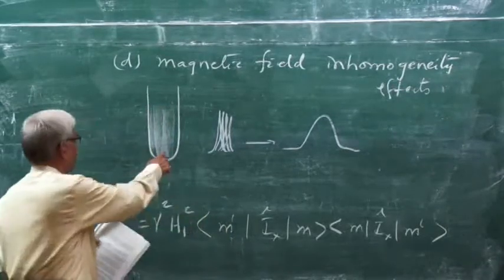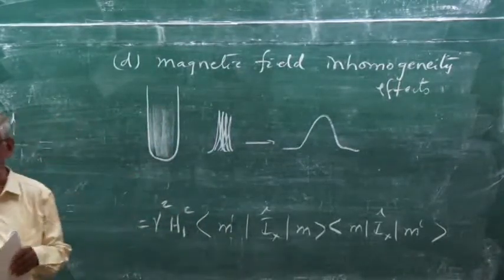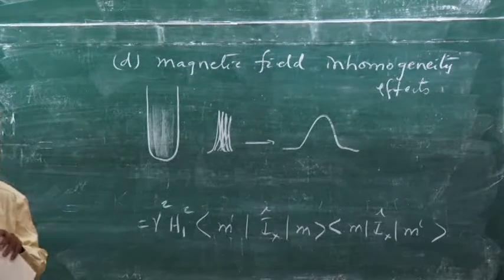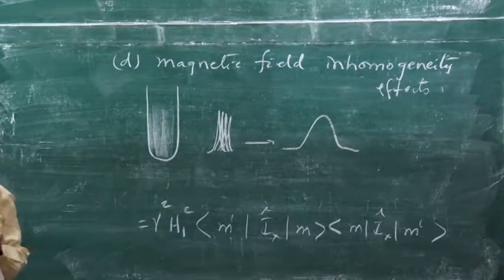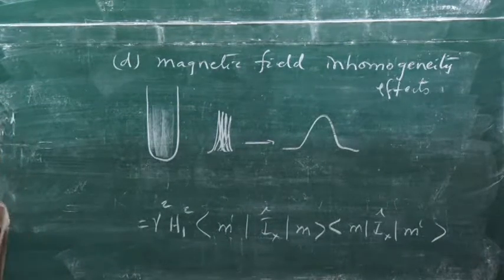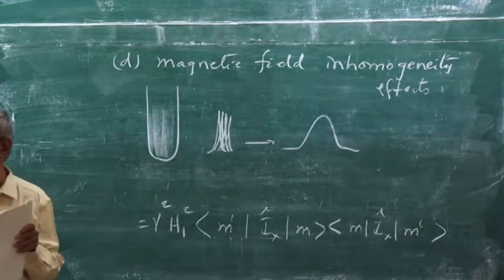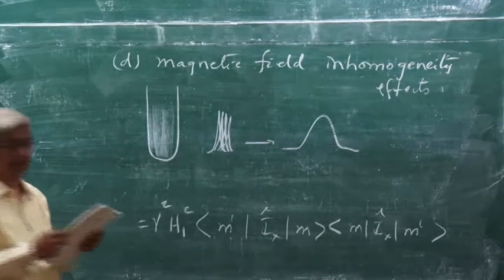You can always improve this by shimming your magnet very well, so that over the sample volume, you have the same homogeneous magnetic field. But those ones, spin-lattice, intrinsic factors, you will not be able to control.